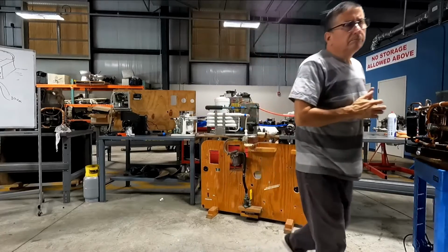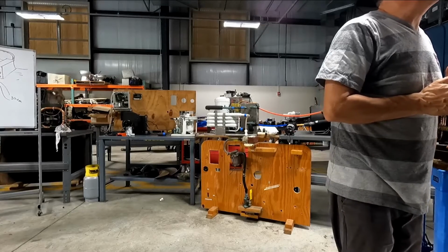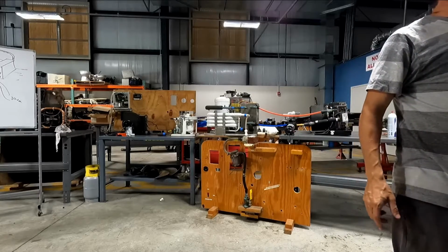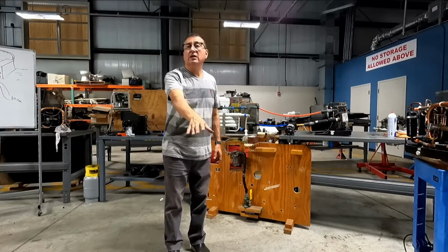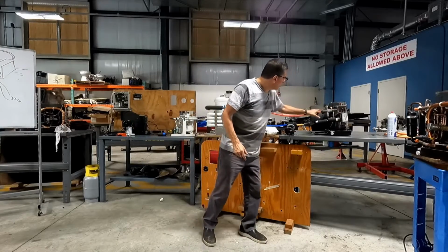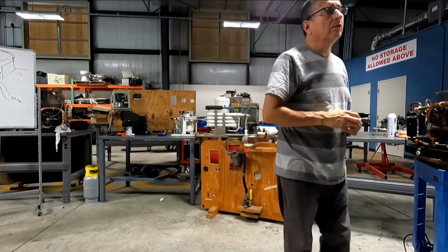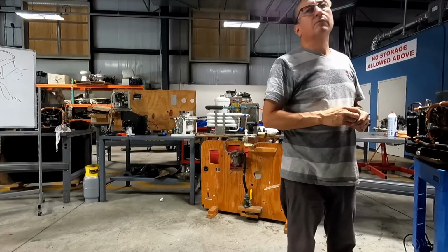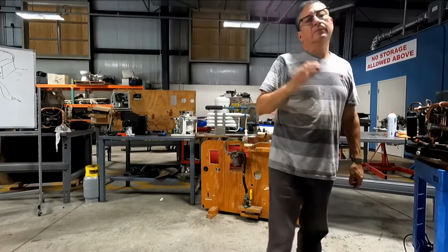You wouldn't even see the refrigerant, would you? Unless you use a dye. Because at ambient temperature it's vapor, so they wouldn't even be able to see it. You're saying she saw the leak and said it's refrigerant, but you wouldn't even see it. In that particular situation, what was the problem? The technician found a lot of coolant on the ground. It's coolant, because one of the pipes, this pipe or this pipe, is leaking. I get that, but it wouldn't even be refrigerant because she wouldn't be able to see it. The Freon would evaporate. So that's how you know it's not Freon, because the boiling point of Freon is negative 22. Not Freon, refrigerant.